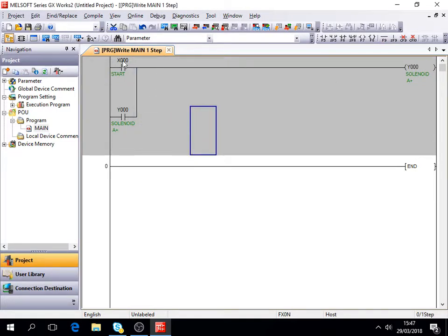So you'll see if I push the start button, power is allowed to flow into the solenoid. Once the solenoid turns on, anywhere it's also labeled as an input, that'll turn on. Now power can come through this direction, so even if I lost power here, it would still have a route through. So it's latched on. Now that'll stay on forever.